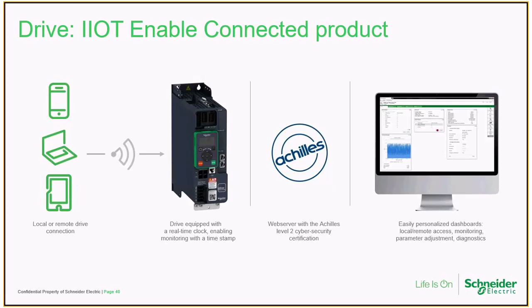If I talk about the best efficiency point of my pump, that can be plotted directly in a graphical view, and it is Achilles level 2. For a highly available network, this drive has two Ethernet ports. With our high performance controller, I can have a ring architecture, making a daisy chain, creating a highly available network on RSTP protocol — Rapid Spanning Tree Protocol — giving high availability to end customers.